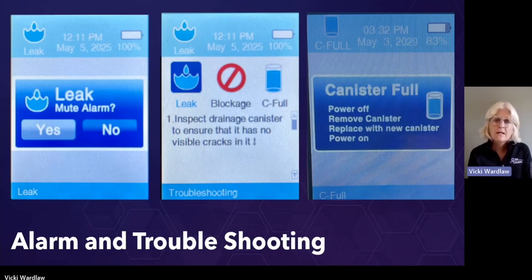For your alarms, you will have a high-pitched beeping noise, and the screen will change, and it will ask you if you would like to mute the sound. That's depicted in that first picture. So this is telling me I have a leak alarm and asking me if I would like to mute the sound while I work on the alarm. It's a pause. It's temporary. It will come back on if you get distracted and don't manage the alarm reason itself. So yes will be highlighted. You can use the center button to select that, and then that will go away, and your instructions for managing that particular alarm will come up next.